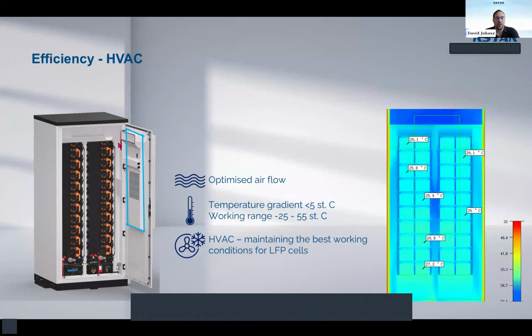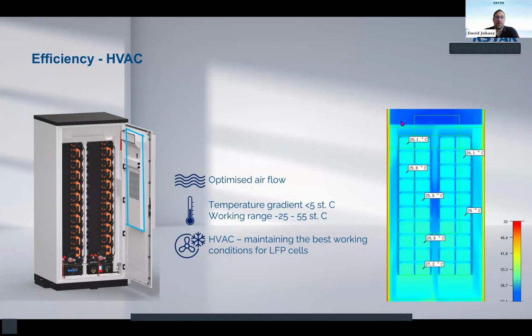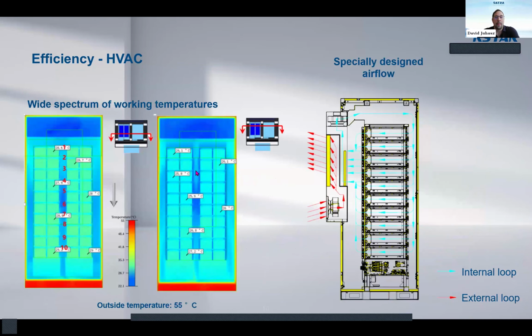There is an air conditioner on the door. This air conditioner has a consumption of 4 kilowatt for cooling and 3 kilowatt for heating. It has optimized airflow, so the temperature difference between the battery packs and cells cannot go more than 5 Celsius degrees. So the monitoring is constant for that. It has an internal loop and an external loop for the air moving, and the design allows efficient cooling of the system.